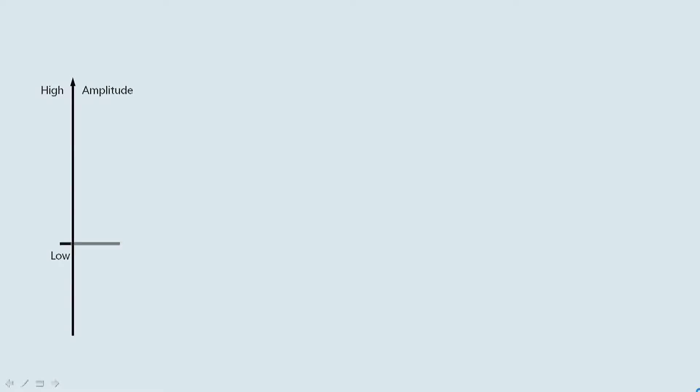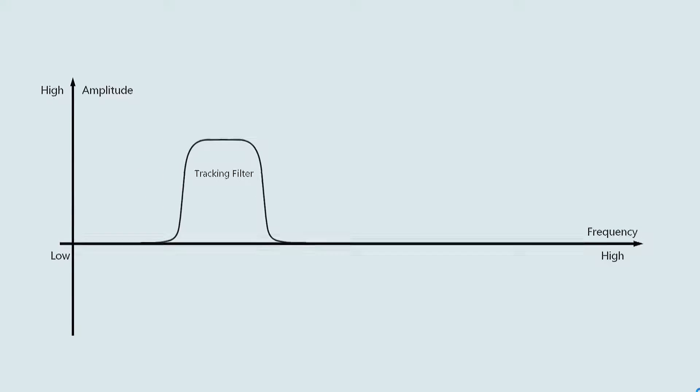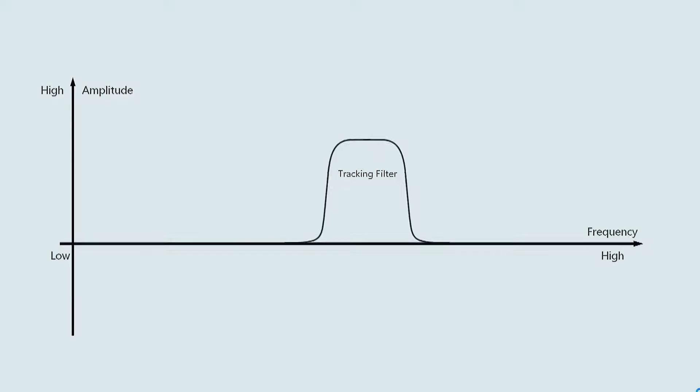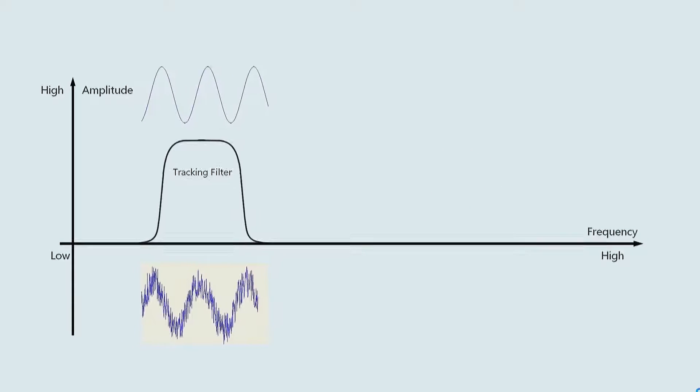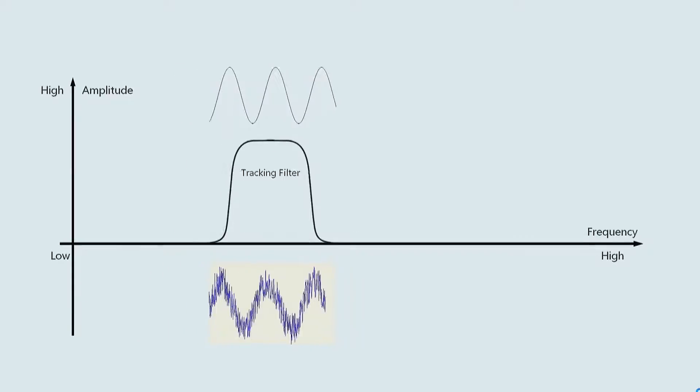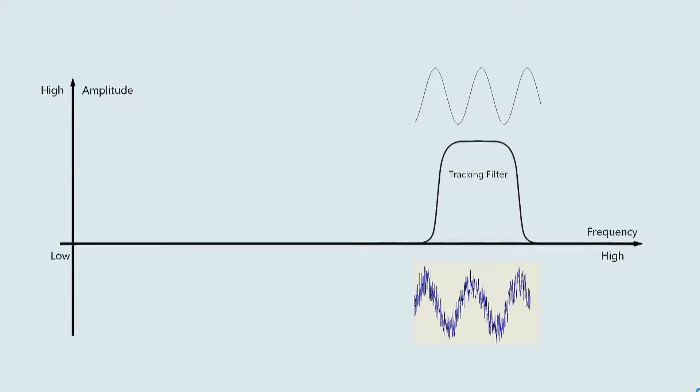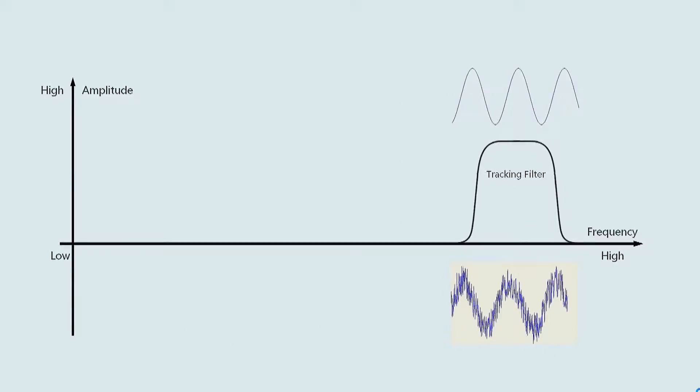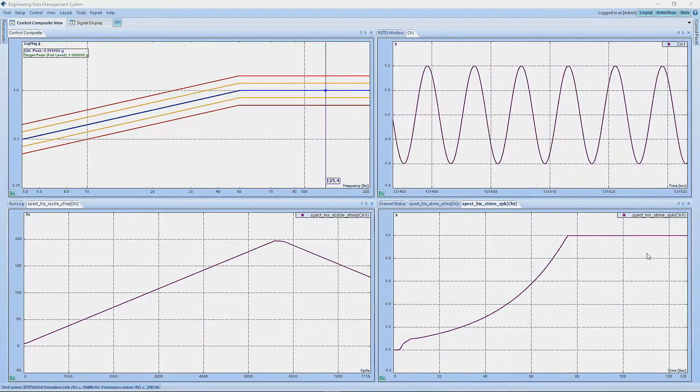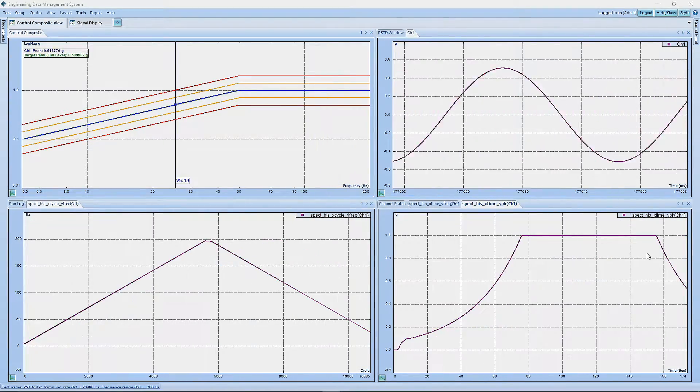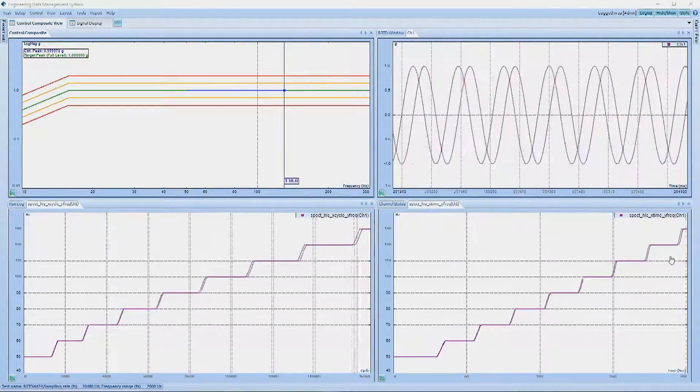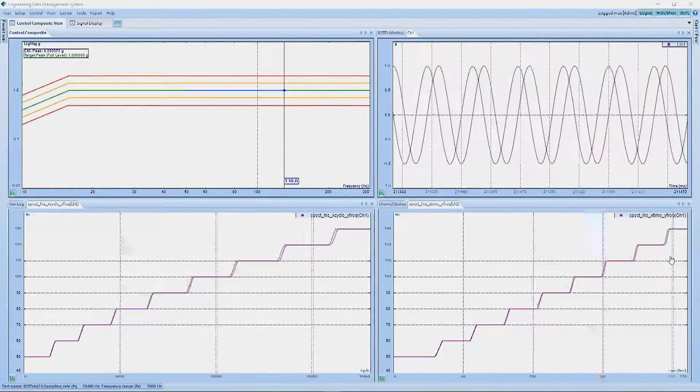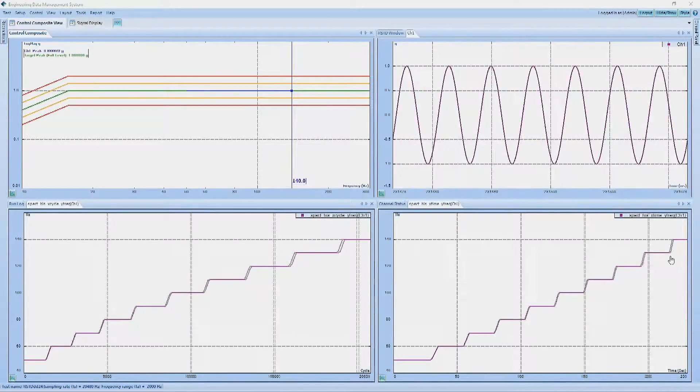Tracking filters greatly reduce noise and the harmonic signals above and below the sine drive frequency. The filter bandwidth can be either fixed or proportional to the current frequency. The SPDR system continually updates the tracking filter coefficients based on the current center frequency and bandwidth.